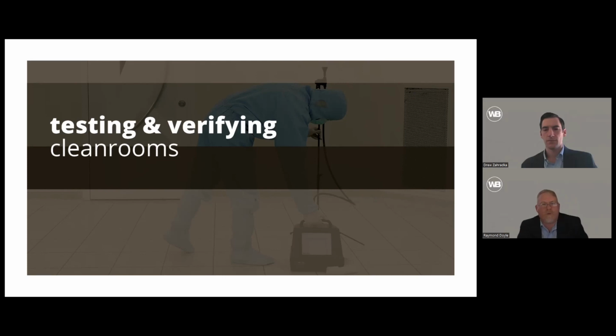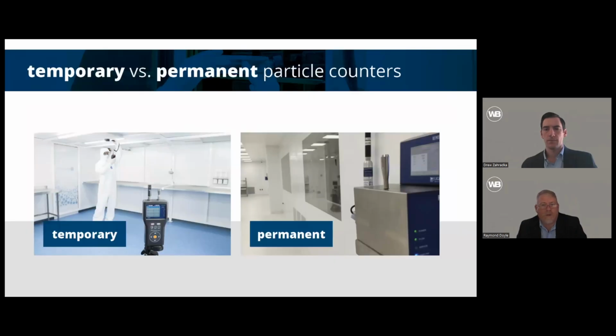But in the simplest form, to test and verify a clean room, you're measuring particles. And you need to make sure that you use a permanent monitoring system, depending on the reporting that you need to provide, if you need daily or weekly or hourly reporting for the science that you're performing. So you might have permanent monitors. And in the case of a lower level verification of something that's certified annually or monthly, or certified on a restart of a project or specific science that might be turning over every month or every week, you can bring in temporary monitors and verify and make sure your space is appropriately classified and verified for the use that you have it.